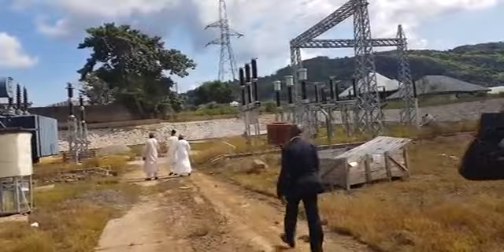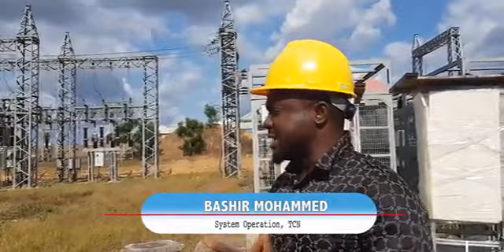The Okene transmission substation has a 90 MVA bulk electricity wheeling capacity serviced by the 2 existing transformers. With the energizing of the 45 MVA transformer, when installation works are completed, right now it's at 90 MVA - that's the 60 MVA and the 30 MVA. So with this 45 MVA coming in, we'll have it at 135.